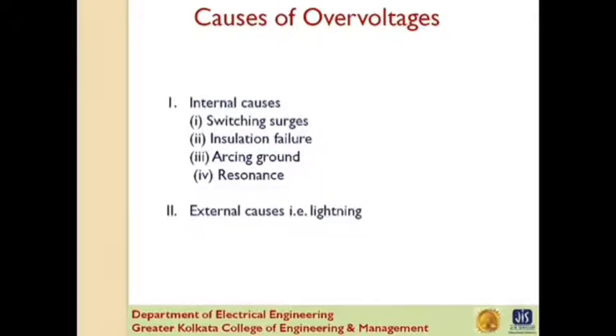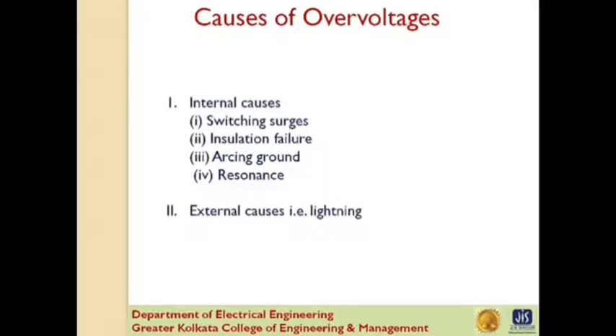However, surges due to lightning are very severe and may increase the system voltage to several times the normal value. If the equipment in the power system is not protected against lightning surges, these surges may cause considerable damage. In fact, protective devices provided against overvoltages mainly take care of lightning surges. Internal causes of overvoltage are primarily due to oscillations set up by sudden changes in circuit conditions, such as a switching operation or a fault condition like grounding of a line conductor. In practice, the normal system insulation is suitably designed to withstand such surges.